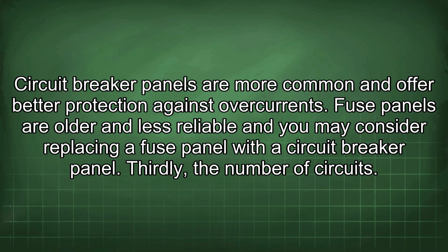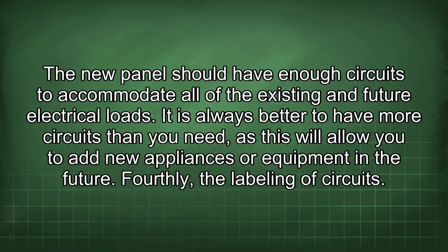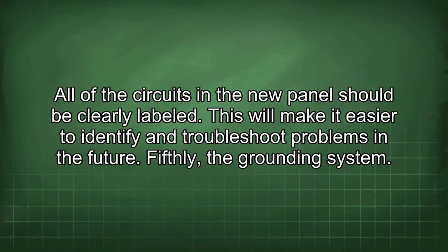Thirdly, the number of circuits. The new panel should have enough circuits to accommodate all of the existing and future electrical loads. It is always better to have more circuits than you need, as this will allow you to add new appliances or equipment in the future. Fourthly, the labeling of circuits. All of the circuits in the new panel should be clearly labeled. This will make it easier to identify and troubleshoot problems in the future.